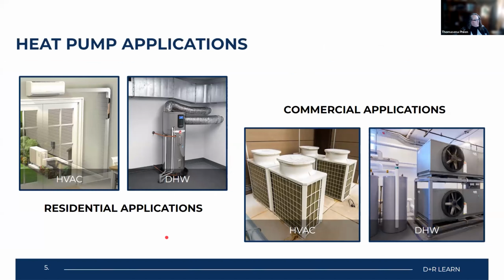Now, we know about heat pumps. Heat pumps have been around a long time. Even heat pump water heaters have been around since the 50s. They started being installed in commercial kitchens because of their innate ability to cool the room while heating water. So it's not a brand new technology, but it is a technology that is being dusted off and reapplied here because inverter technology is a thing now. Improved coil sizes and function is a recent addition. And so what we have here is your inverter mini split heat pump.